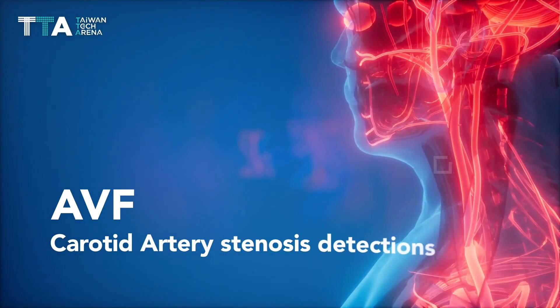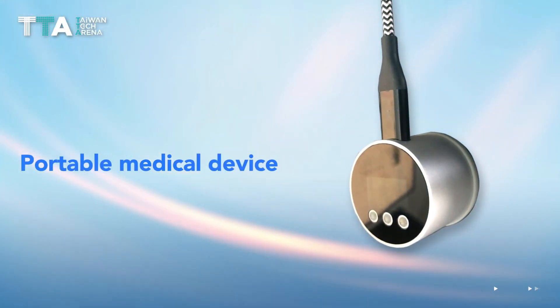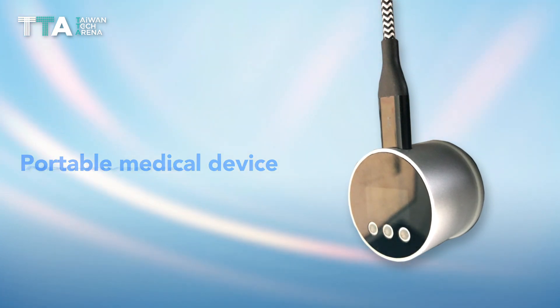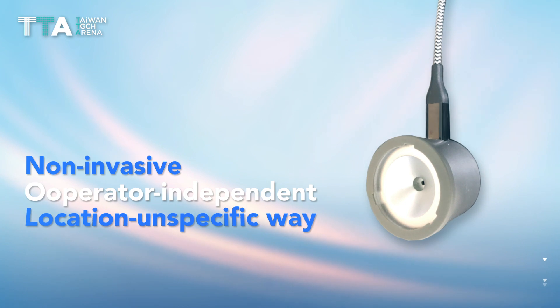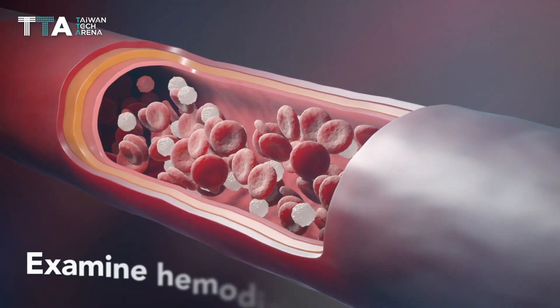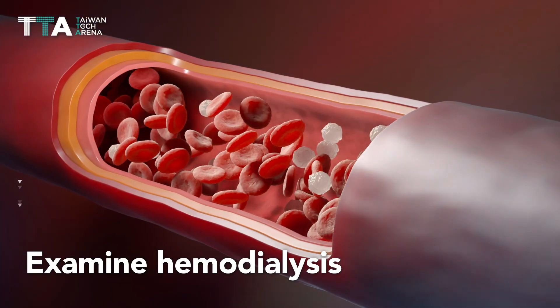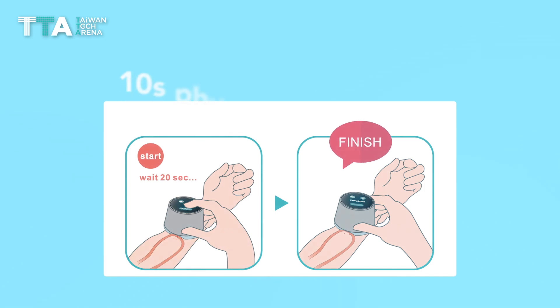AVF and carotid artery stenosis detection is a one-stop solution with a portable medical device to detect dialysis access stenosis in a non-invasive, operator-independent, location-unspecific way, to examine both hemodialysis and potential stroke patients.